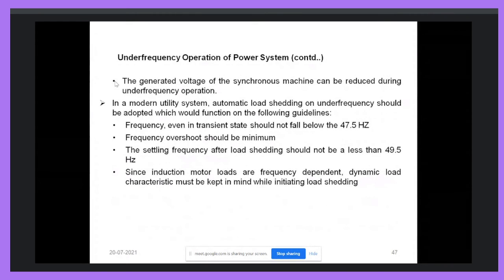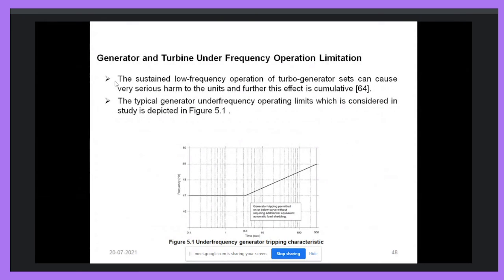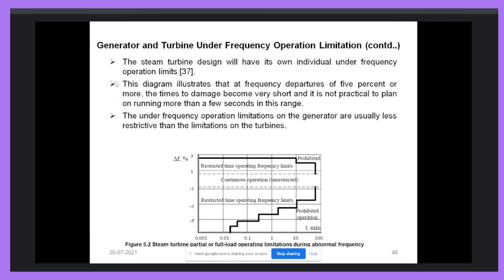Okay, so here you can see this is the particular under frequency generation tripping characteristic. Okay, so the generator must not operate below this. Suppose here you can see a dark line, which is at 47 hertz. So below that frequency for a particular time, suppose 3.3 seconds, we can operate the generator at this lower frequency for this particular time only. If the time increases, we have to separate the equipment from the system. Okay, for that we have to design a load shedding technique. This is the particular operation restriction of the generator for under frequency operation.